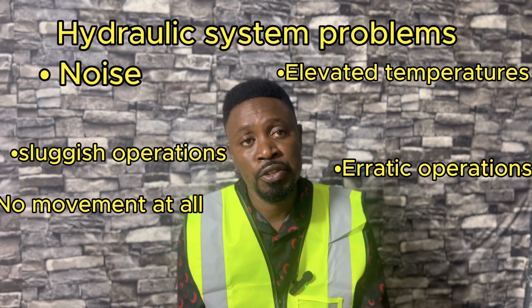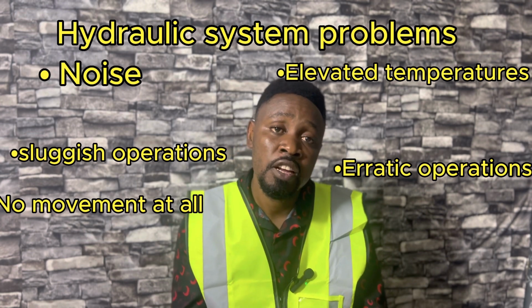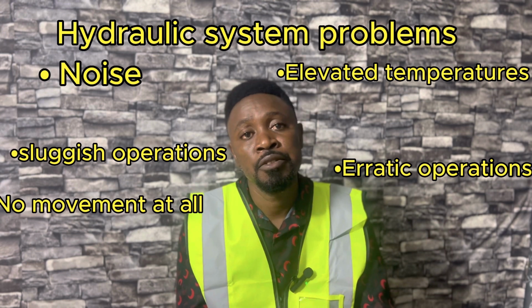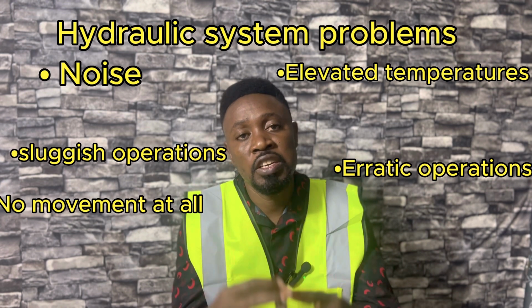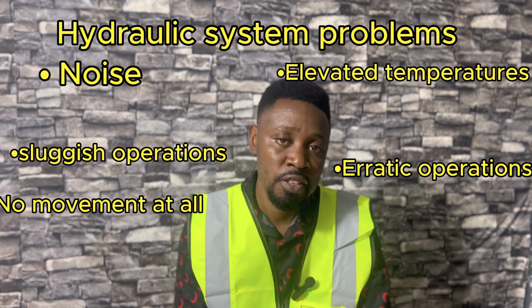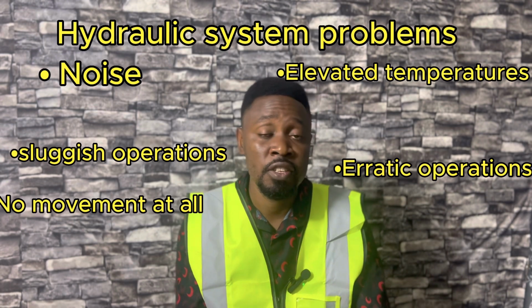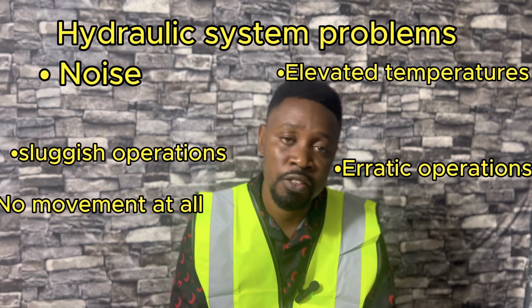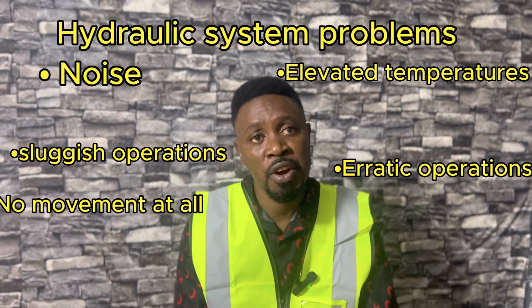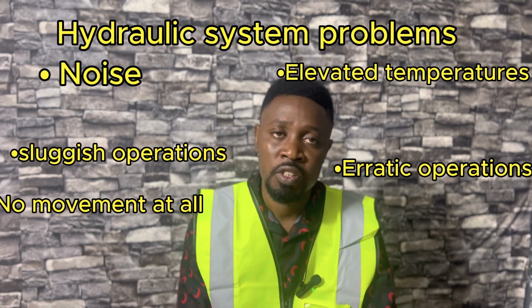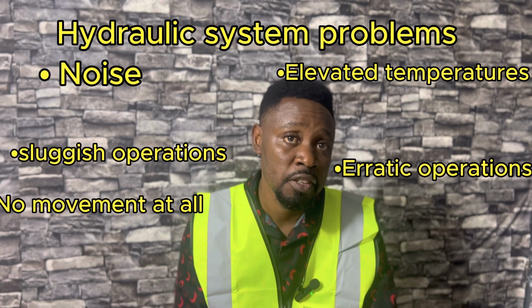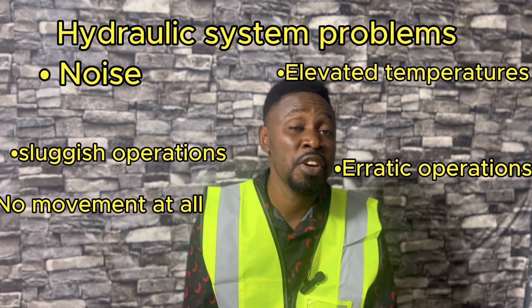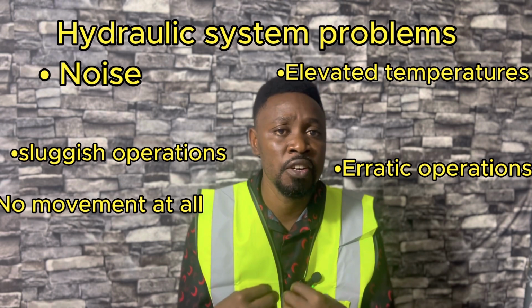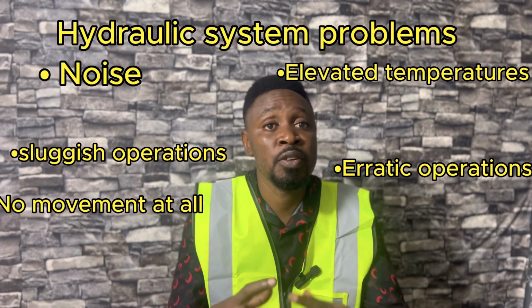Now, when we talk about cavitation, cavitation comes with liquid or water finding its way into the hydraulic system. Now, this also causes similar noise. We've talked about cavitation already, so we'll move on. Now, apart from those two, you could hear metallic noise. Now, this is very severe, and you could hear as if there are marbles within the pump as the pump rotates.